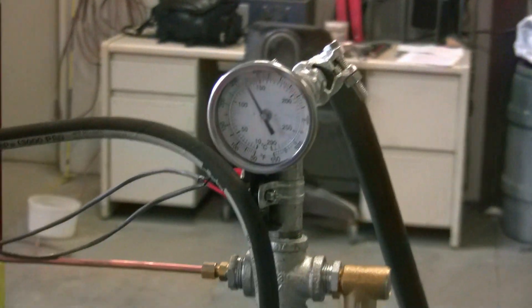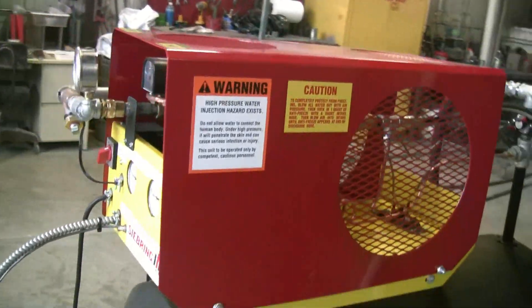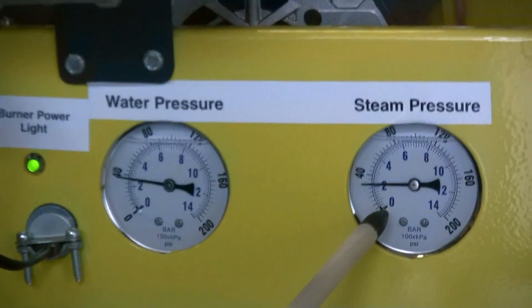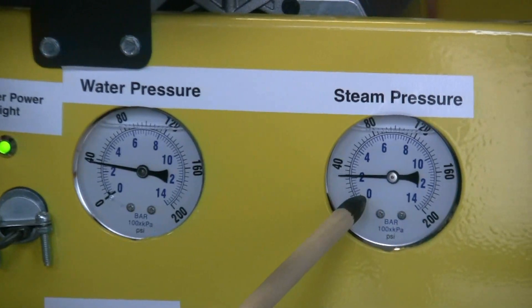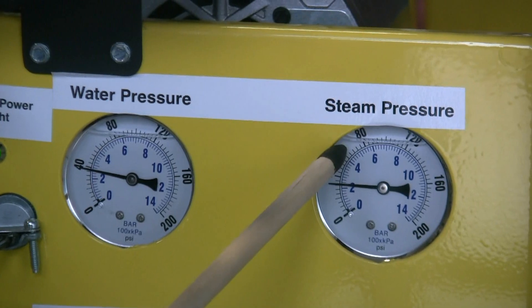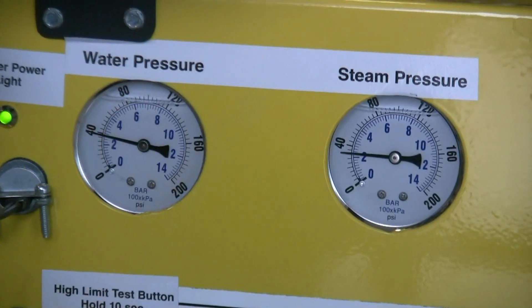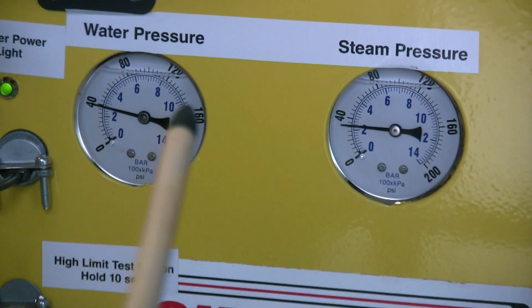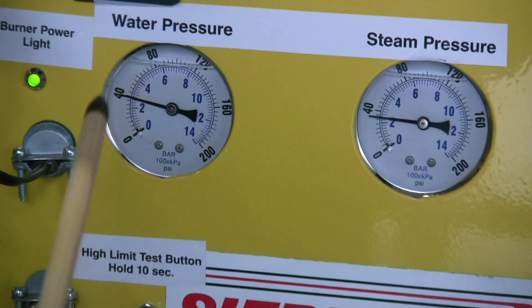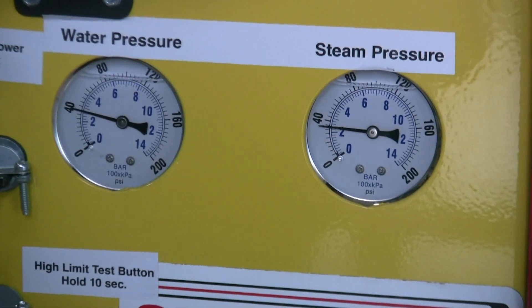You can see the water pressure — about 40 psi — and the steam pressure is about there too, slightly lower. On this SG15 it will be about 70 psi for steam and the water pressure will also be 70 psi. Once the water pressure goes up above the steam pressure, that means the coil is becoming plugged and will need to be de-limed.